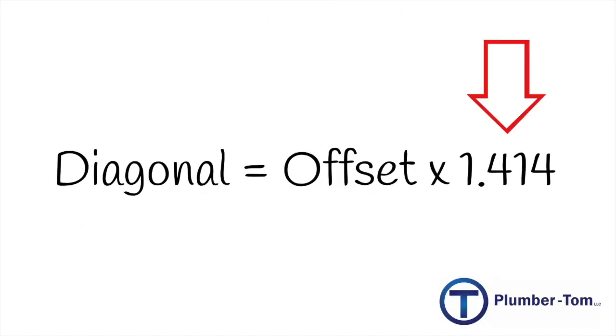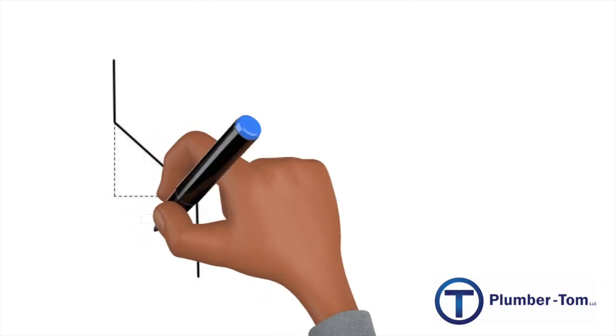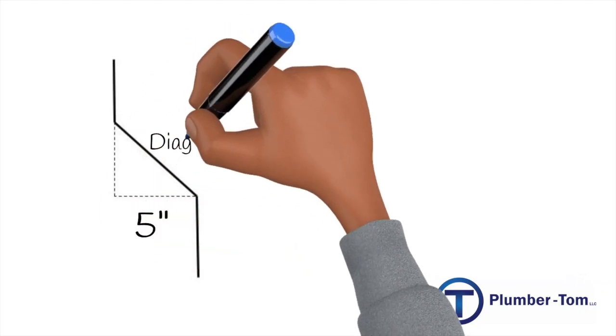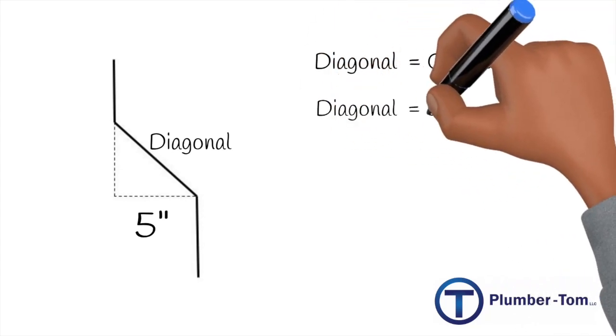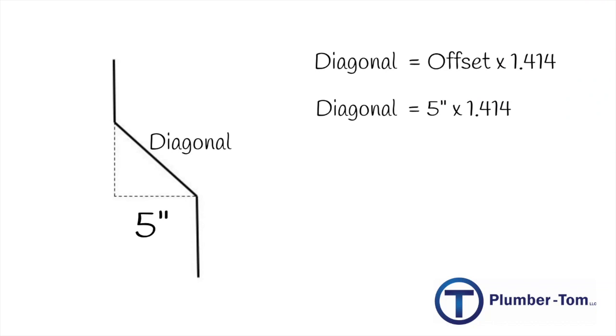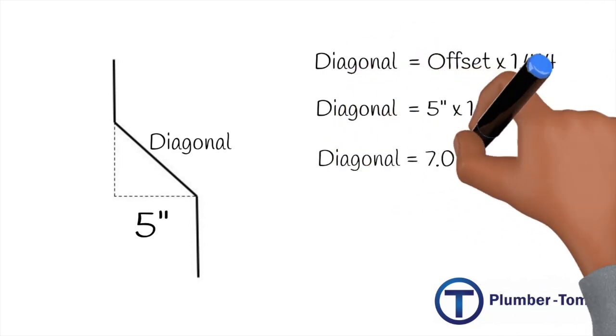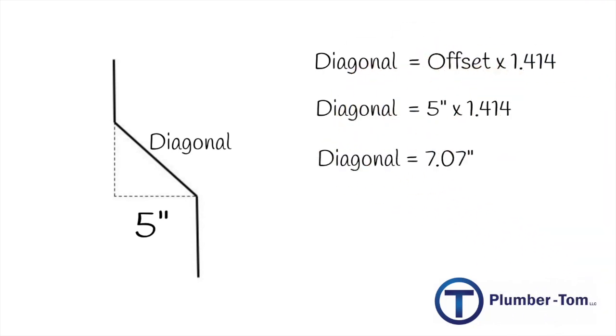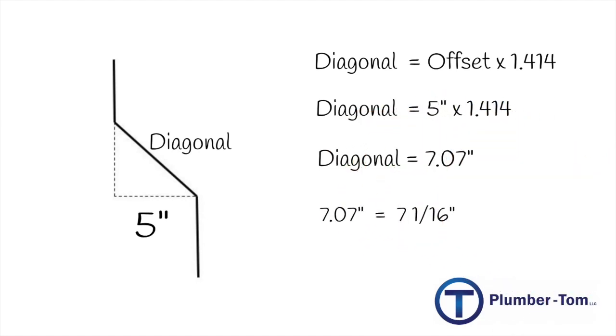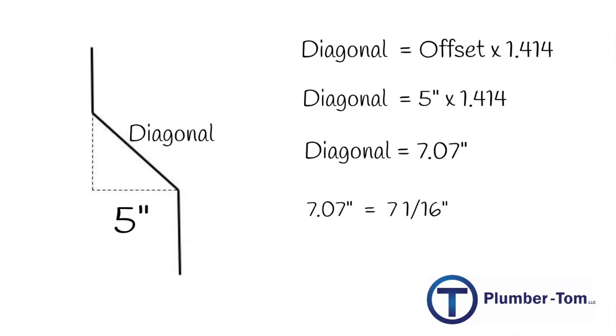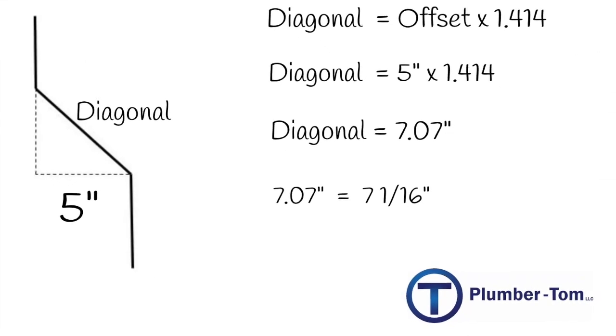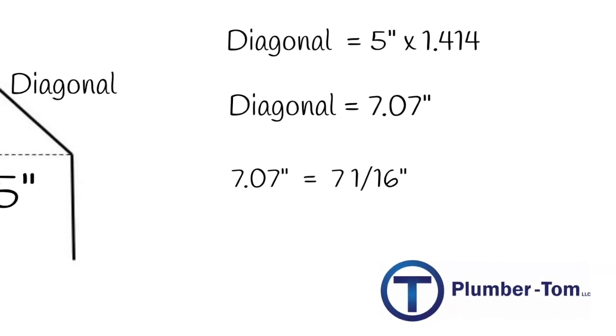Let's look at an example as we calculate for the offset. What if the offset is five inches, and we want to find the diagonal, which is where our pipe will run. We will take the offset, which is five times that by 1.414. And on a calculator, we will find 7.07. Now if we were to convert that into fractions of an inch, you will find that it is 7 and 1 sixteenth of an inch.